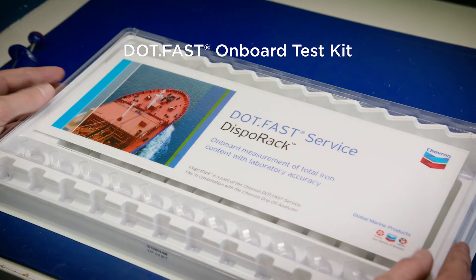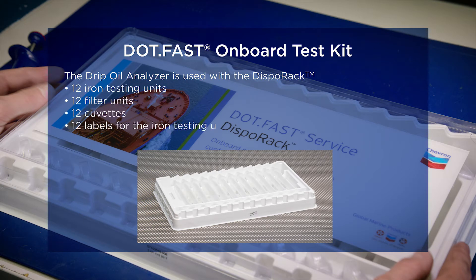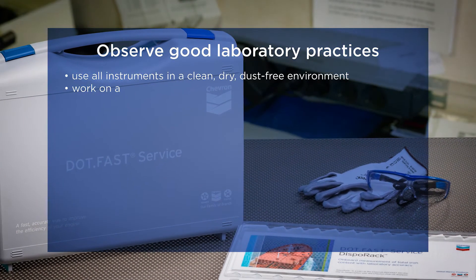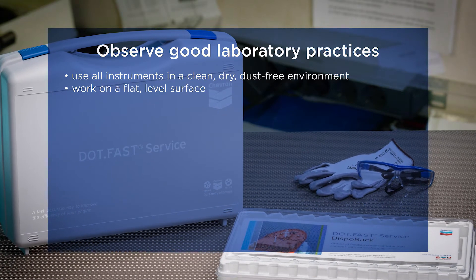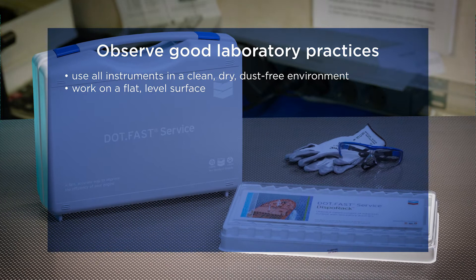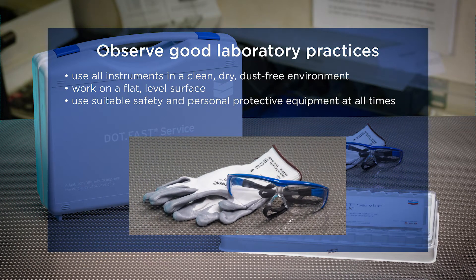The drip oil analyzer is used in combination with a DISPO rack. One DISPO rack contains 12 iron testing units, which allows for 12 cylinder drip oil sample analyses. All analysis instruments should be used in a clean, dry, dust-free environment and placed on a flat, level surface. Suitable safety and personal protective equipment such as safety goggles and gloves must be used at all times.